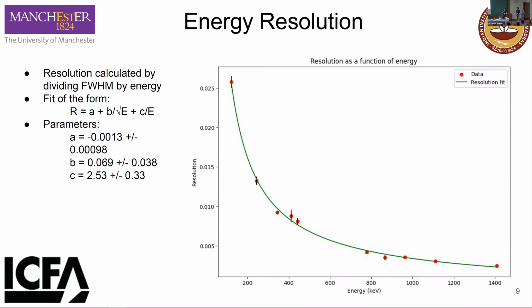Okay, then the second thing we do is the energy resolution. Again, putting a Gaussian across each peak, in this one we take the full width at half maximum from the Gaussian peaks. You divide this by the energy, and this would be the resolution. Then we fit this form here and put in the data. There's a slight shift caused by a, you can see, but the shape is dominated by these two terms.